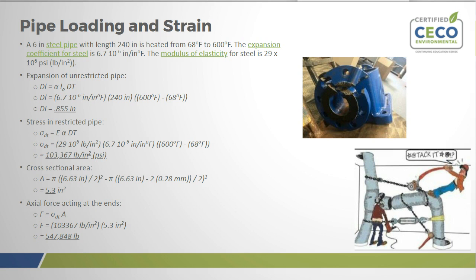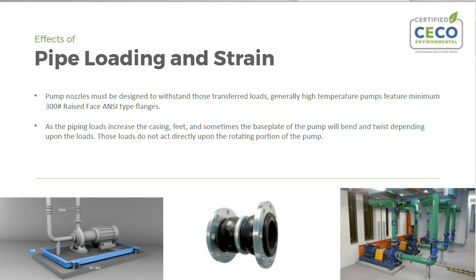Now, of course, the pipe will not remain restricted. It will break bolts. It will break flanges. As you can see, it will bend and twist the pipe, the pump, the piping. It will do everything it can not to be restricted. It's going to move no matter what you try to do. So the way to do it is to mitigate that movement, and the way that's done is basically to use expansion joints, flexible couplings.